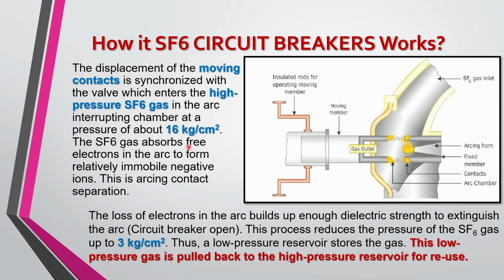The SF6 gas absorbs free electrons in the arc to form relatively immobile negative ions, and this is arcing contact separation. The loss of electrons in the arc builds up enough dielectric strength to extinguish the arc when the circuit breaker opens. And this process reduces the pressure of the SF6 gas up to 3 kg per centimeter square. So there is an appreciable reduction in the gas pressure from 16 kg per centimeter square to 3 kg per centimeter square.